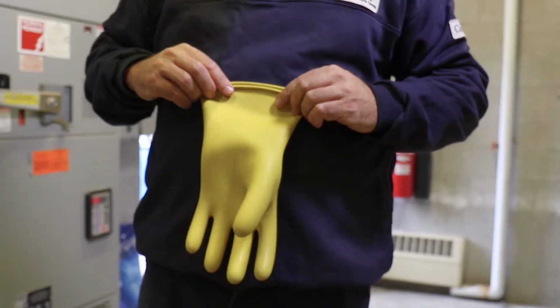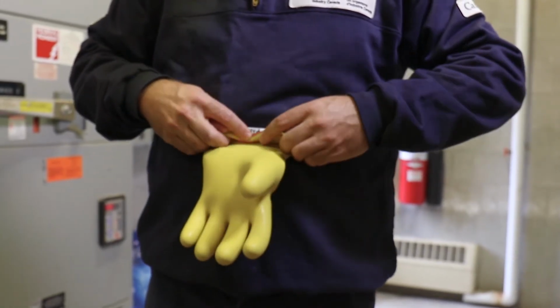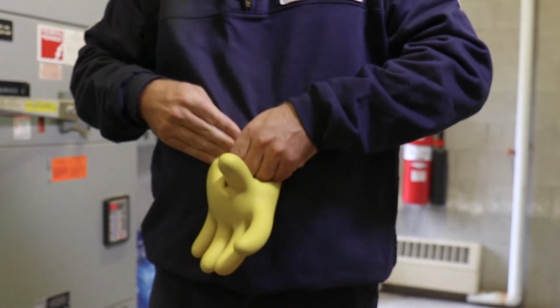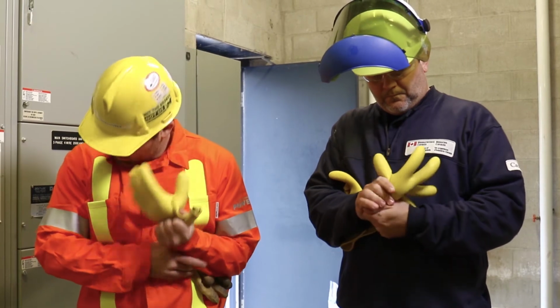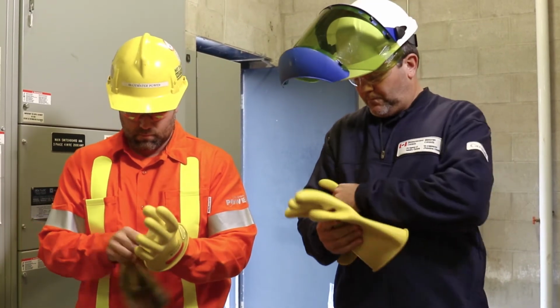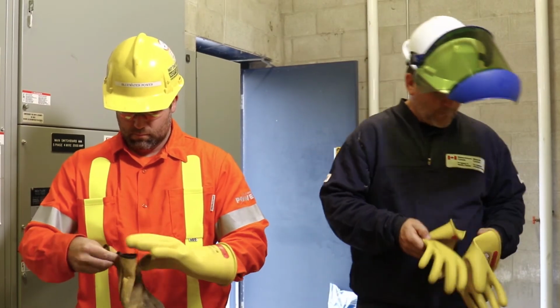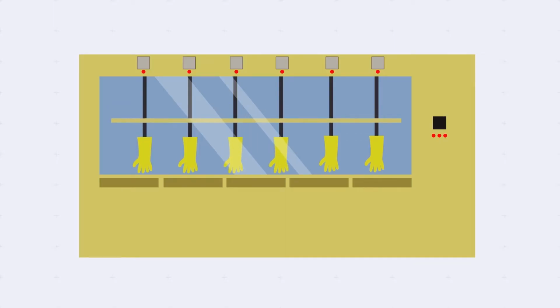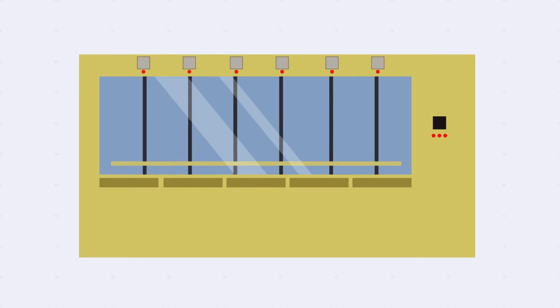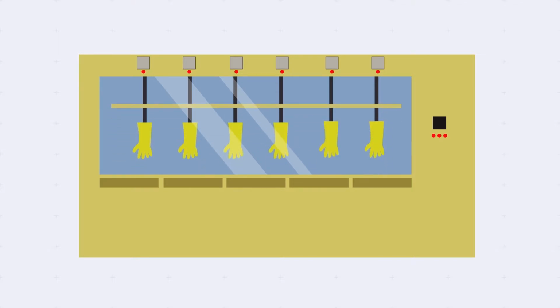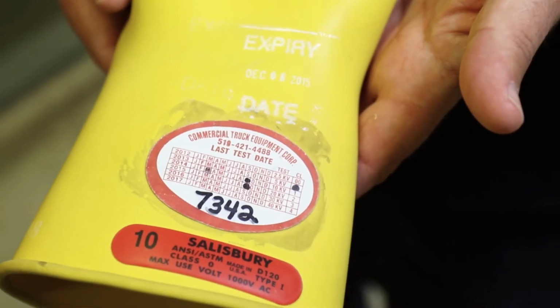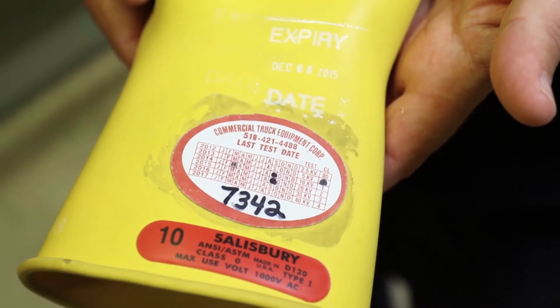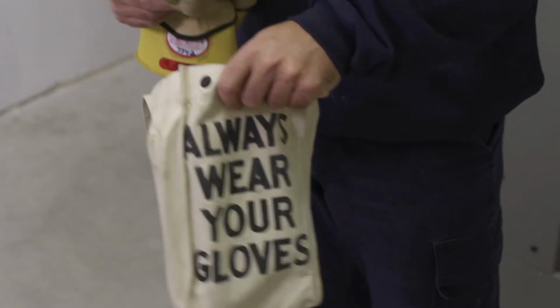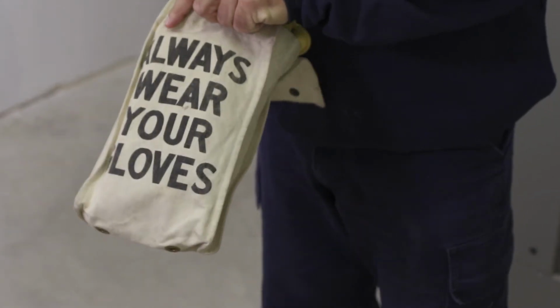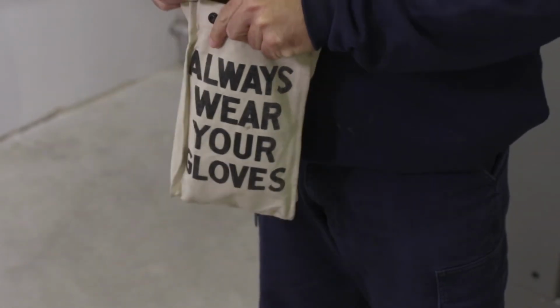The air leak test is performed by holding the glove cuff with your thumbs and forefingers and twirling it around quickly to fill it with air. Squeeze the glove, then look and listen for escaping air. Examine your gloves closely for embedded foreign materials or surface contaminants that could impact their performance in any way. Ensure that rubber insulating gloves are tested with a dielectric test at least once every 6 months, and destroy any gloves that are defective. Always wear gloves right side out, with the serial number and size on the outside. Gloves should be stored in a protective case, typically a canvas bag, to protect them from sharp or pointed tools that may puncture them and from UV light.